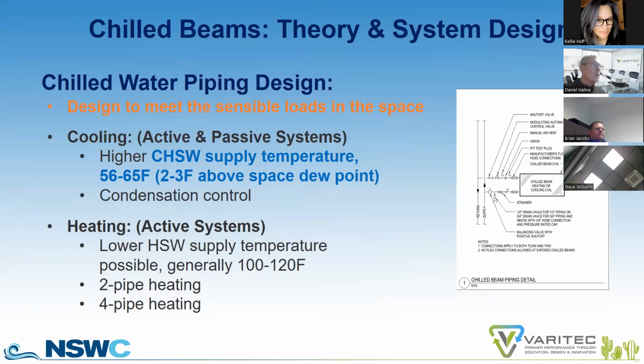Again, chill water is supplied at 2 to 3 degrees above space dew point. Active chill beams come in 2-pipe heating or 4-pipe heating configurations. I was involved in 2 articles with ES Magazine and an engineering team from Smith Group that evaluated what happens when room dew point rises to 2 degrees above space dew point.